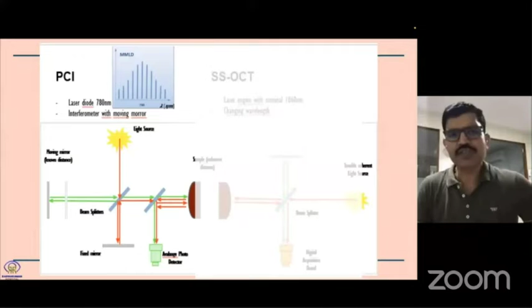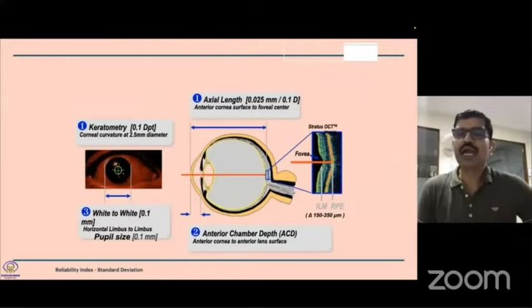a constructive interference. The machine gave us very good readings regarding axial length, regarding keratometry, regarding white to white, but the anterior chamber depth was a slit beam reflectometry technology and not an actual measurement, and it also did not give us lens thickness.